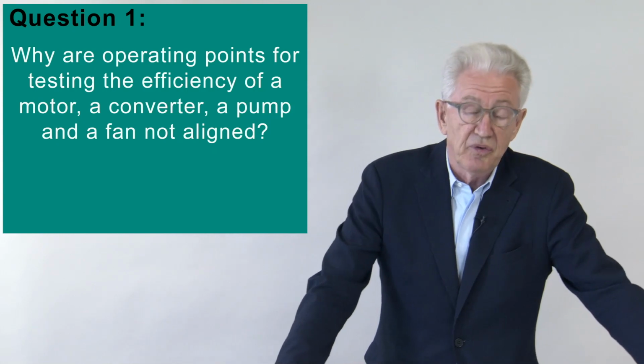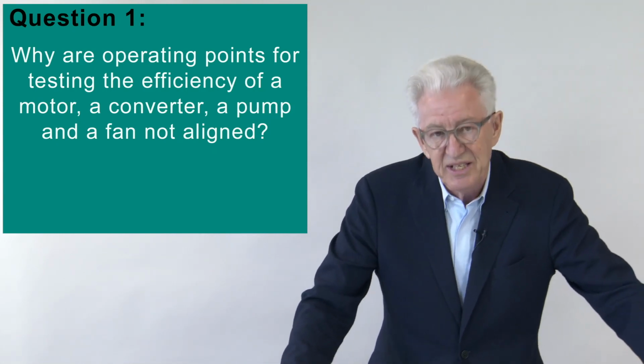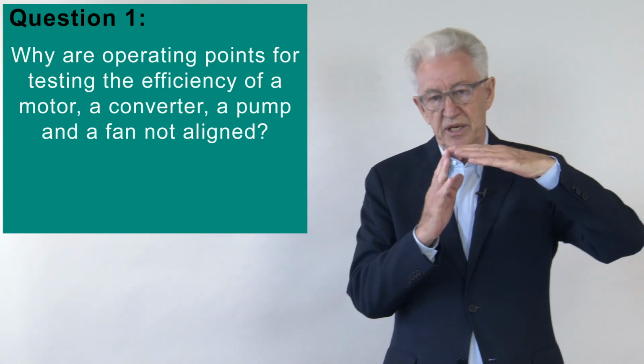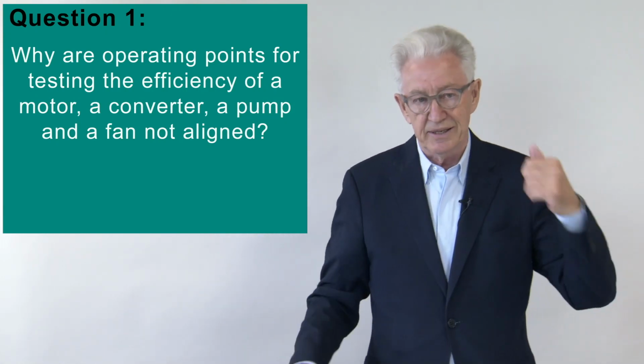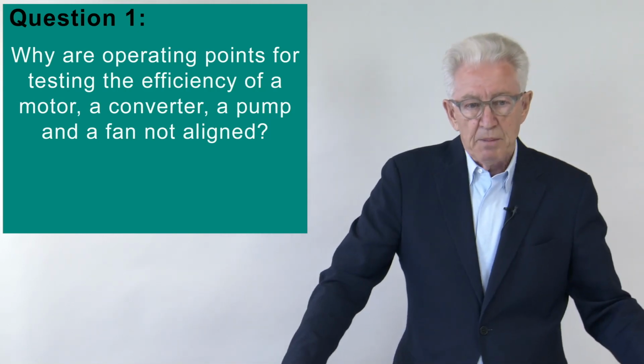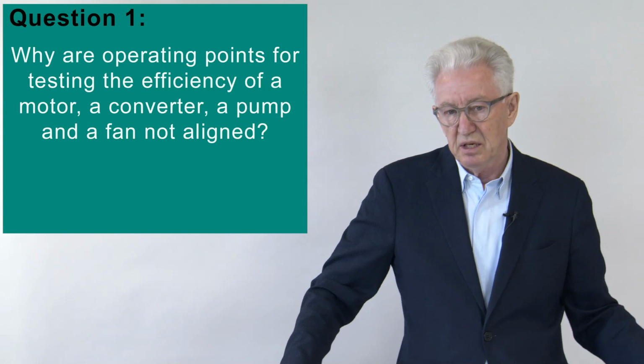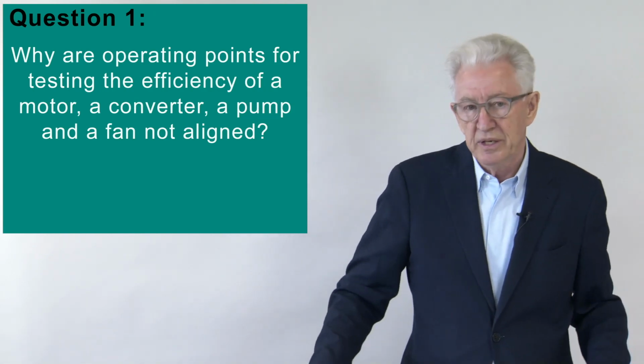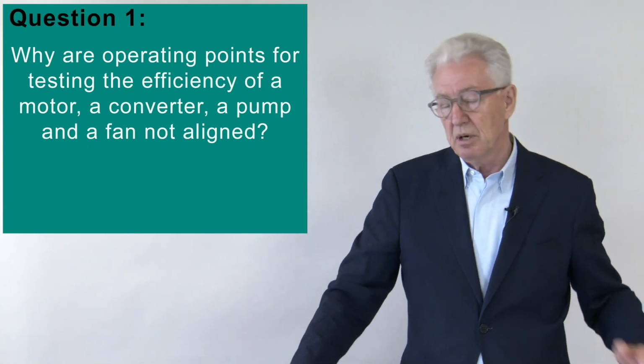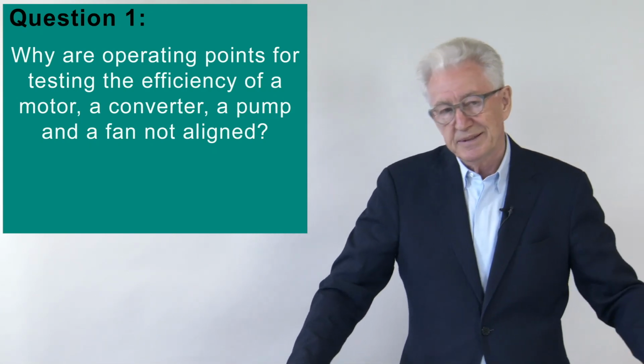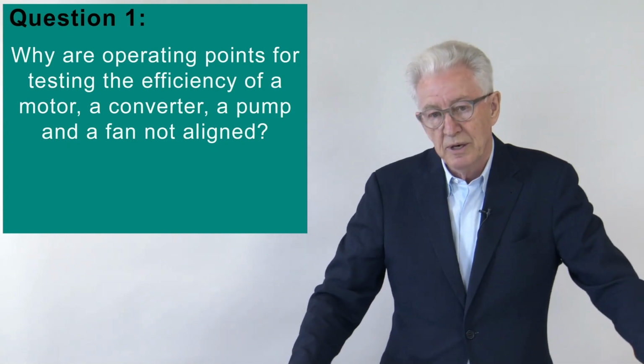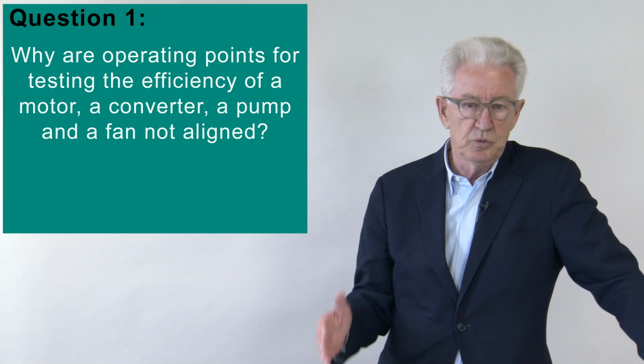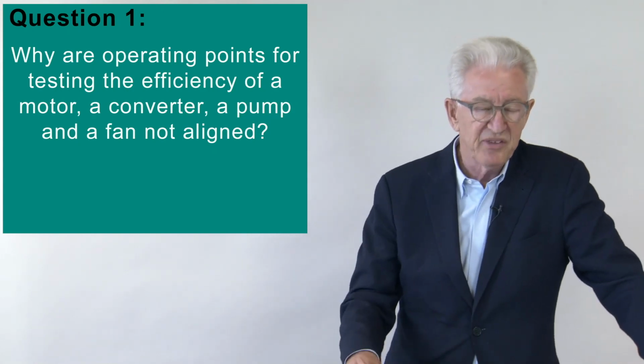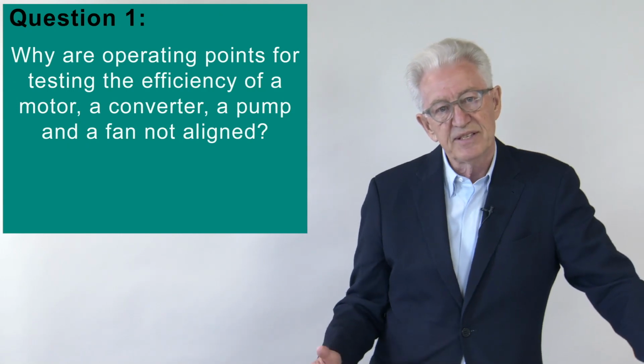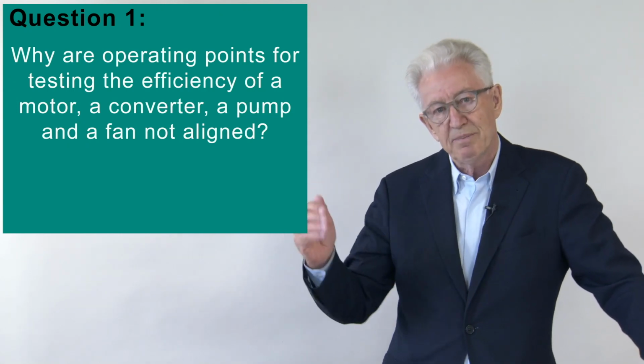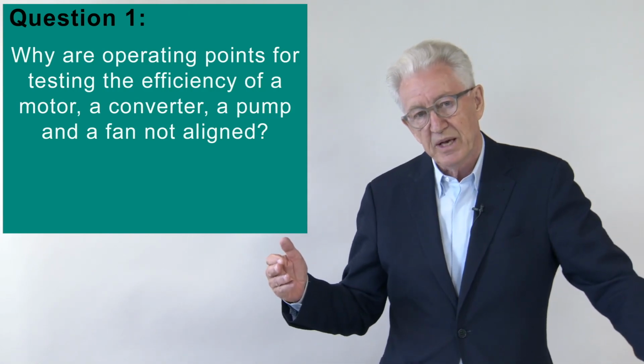Motors, and converters the same, are usually tested at around their nominal or rated power, which I showed in this diagram, the contour curves with the white dotted line, at 100% torque and 100% speed. But a pump or a fan is usually not operating there. It operates at its best operating point, which might be 80% of the speed or 120% of the speed, and might be 60% of the flow or 80% of the flow. Therefore, the motor people have to start testing and having interpolation methods so that they can deliver their efficiency values to the pump's requirements, the fan's requirements, and the compressor's requirements.